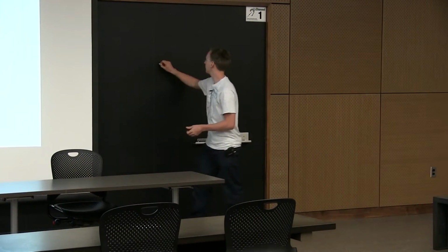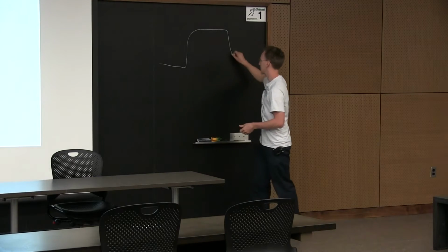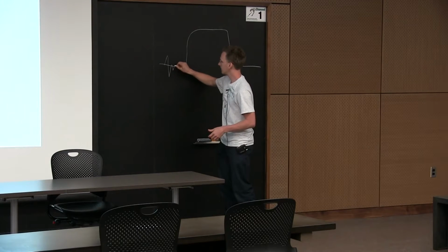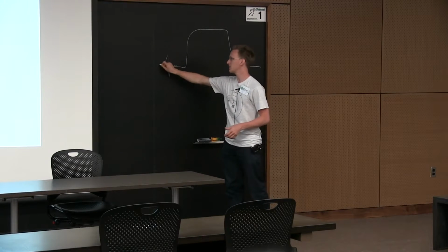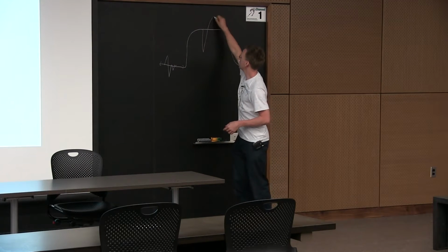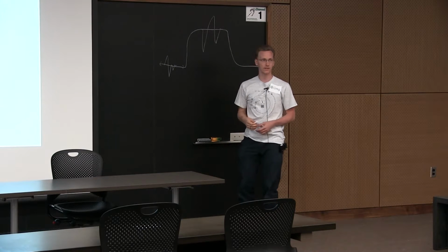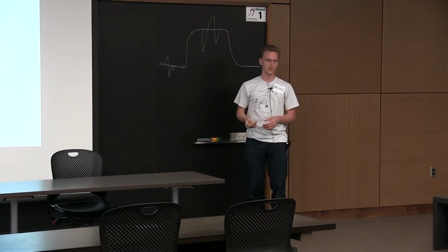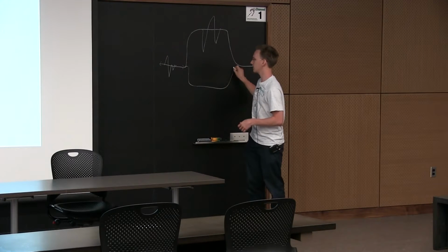Here's a fluorescence trace, the simplest possible thing. One thing we do is say, if this is noisy, because we use this as part of the measurement, tell the user. If standard deviations are above certain levels at certain critical points, tell the user. If this goes in the opposite direction, tell the user.